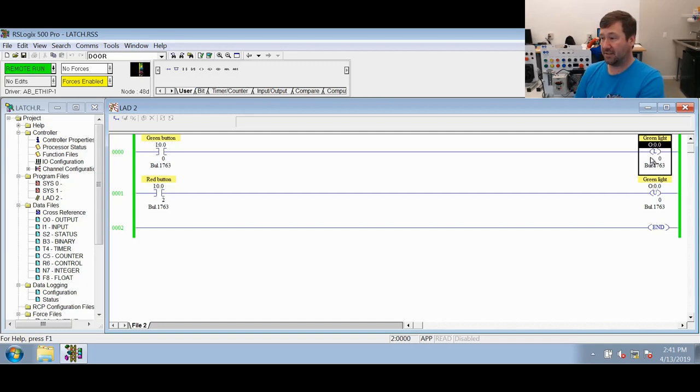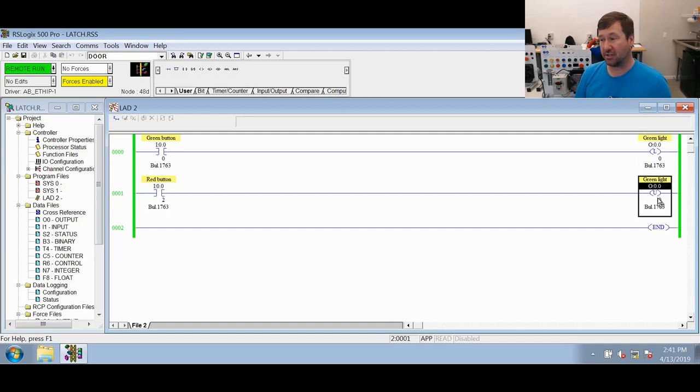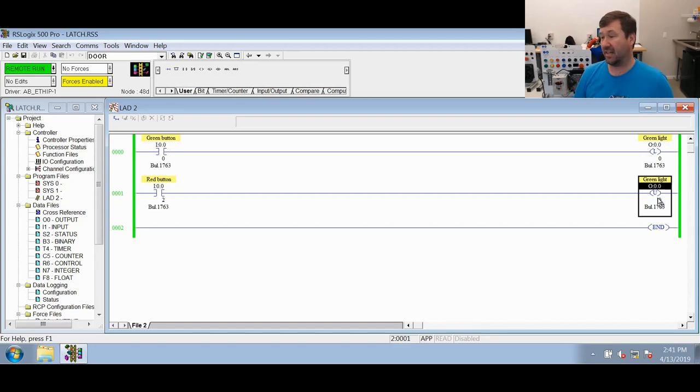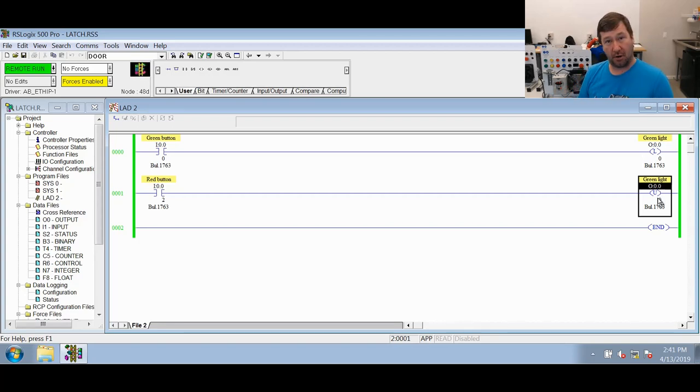So same, our OTU instruction, if it is true, it writes a zero. If it is false, it does nothing. So again, the most important part to take away from this is there's not something magical somewhere that is holding these latched. An OTL simply can't go write a zero to that output. So as long as nothing else ever goes and writes a zero to it, such as an OTU, then it will continue to have a one in it.